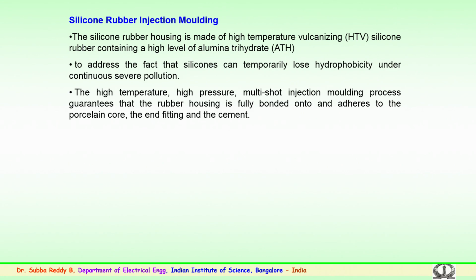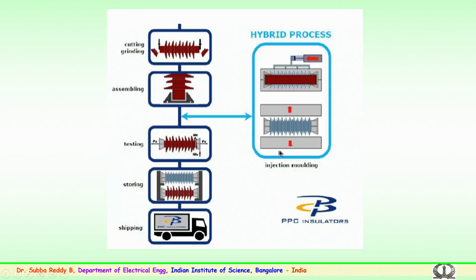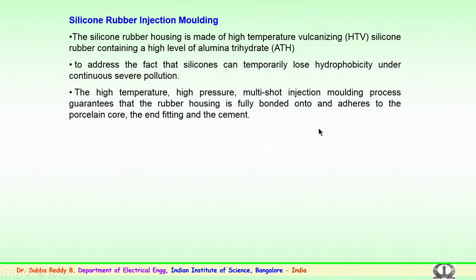This addresses the fact that silicones can temporarily lose hydrophobicity under continuous severe pollution or contamination environments. So, the high temperature, high pressure multi-shot injection molding process guarantees that the rubber housing is fully bonded and adheres to the porcelain core. As mentioned earlier, the core of the insulator assembly is porcelain. The core of the insulator inside is the porcelain, and on that are the polymer or silicone rubber sheds, which are embedded on it. So, this high temperature, high pressure multi-shot injection molding process guarantees the rubber housing is fully bonded onto the porcelain core, and the end fittings and the cement.